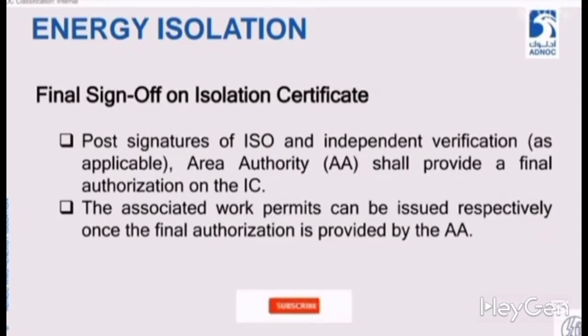After verification, it will proceed to the area authority. The area authority will verify everything to ensure that our isolation points have been properly isolated at the right points. A zero energy demonstration has been conducted. The signatures of both parties were applicable there and have been done. After that, the area authority will sign it and our isolation confirmation certificate, the ICC, will become live. Next, our task is to make the associated work permit live.